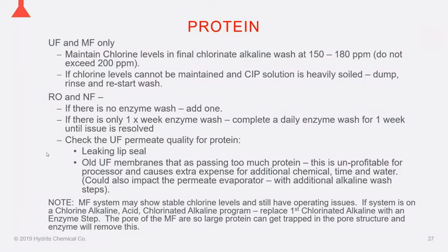In both cases, just referring back to the ultimate solution to this, if this system is going to need a wash that's going to improve upon its proteolytic activity because they've changed the process, that's one thing. But if this system is not supposed to have seen a lot of protein, and it suddenly is, chances are we need to look upstream for the problem for a long-term solution.